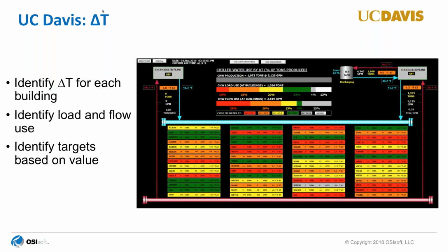So now it gives you where to start identifying what's available to you, the pumping demand, how much adjustment in the building versus the system can you make? Are there other things that we need to do from a chilled water point of view? Because this thermal energy is expensive. And so this was a way to get started and look at continued big picture things. They also do have energy storage up on the right, so they are able to compensate by energy storage and discharging during peak times. But again, we still need to focus on where that 30% flow is causing us performance issues on the efficiencies of systems.